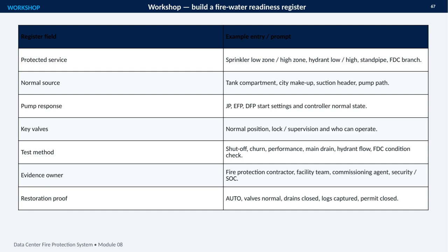Finally, assign an evidence owner, so responsibility does not disappear between contractors, facility staff, commissioning, and security operations. The most important field is restoration proof. Confirm pumps are in auto, valves are normal, drains are closed, logs are captured, and any permit is formally closed.